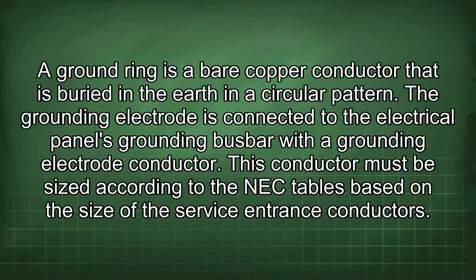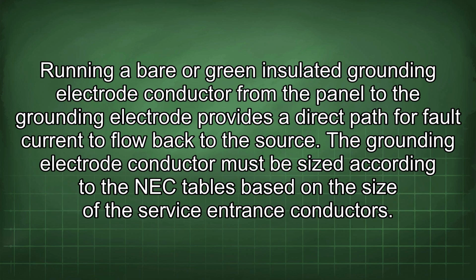The grounding electrode is connected to the electrical panel's grounding busbar with a grounding electrode conductor. This conductor must be sized according to the NEC tables based on the size of the service entrance conductors. Running a bare or green insulated grounding electrode conductor from the panel to the grounding electrode provides a direct path for fault current to flow back to the source.